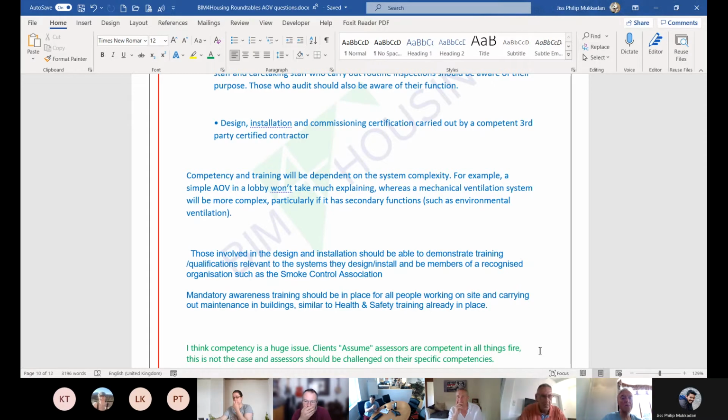So the competency of the person that had been checking that should have been flagged up way before that. But because it said fire door on it, the people checking it assumed that it was a fire door. I think we really need to nail the on-the-ground competency of the people undertaking these checks and balances, and not only the companies undertaking them.